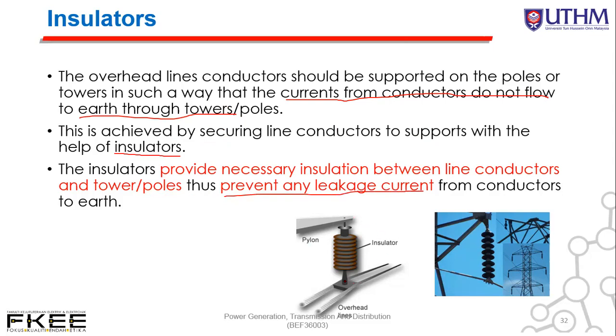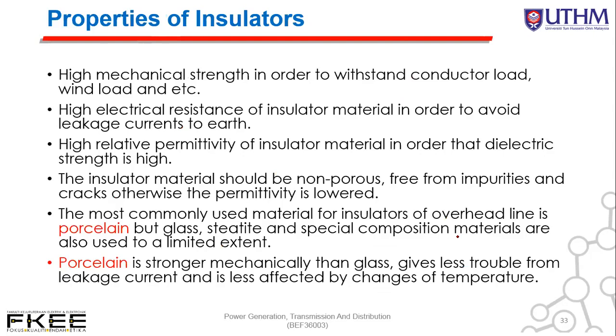The insulator protects the current flow from the conductor to the cross arm or to the tower. Properties of insulators must include: high mechanical strength to withstand conductor load, wind load, etc.; high electrical resistance of insulator material to avoid leakage current; and high relative permittivity so that the electric strength is high. Insulator material should be non-porous, free from impurities and cracks. The most commonly used material for insulators on overhead lines is porcelain, because it is stronger mechanically than glass, gives less trouble from leakage current, and is less affected by changes of temperature.